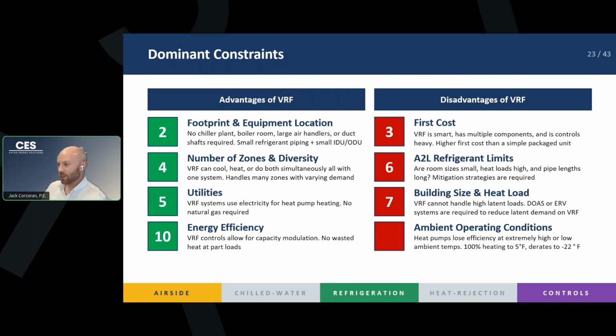And the second disadvantage, right, we're running A2L refrigerants through these VRF systems. A2L is slightly flammable. It's a type of refrigerant class. We used to be able to run A1 refrigerants, which were not flammable at all. Now we're stuck using A2Ls. And there are all sorts of mitigation strategies that we didn't have to contend with before that are now required. So, at a high level, you want less refrigerant in order to stay under the concentration limits. So if you have small rooms or you have large heat loads and long pipe lengths, maybe this isn't the best system because you're going to have to implement mitigation strategies.